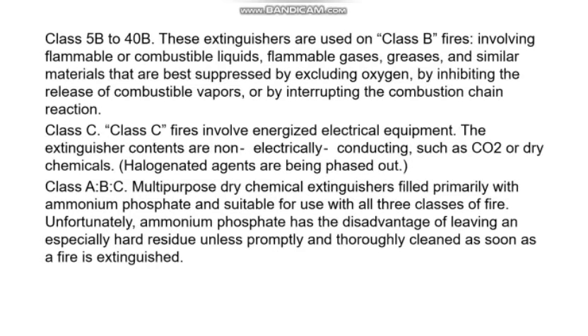Next is Class 5B to 40B. These extinguishers are used on Class B fires involving flammable or combustible liquids, flammable gases, greases, and similar materials that are best suppressed by excluding oxygen, by inhibiting the release of combustible vapors, or by interrupting the combustion chain reaction.